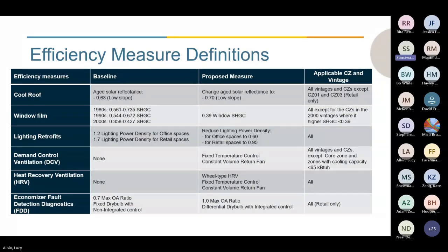And the fifth measure is heat recovery ventilation, or HRV. This measure is a mechanical device intended to remove air from buildings, simultaneously replacing it with outdoor air, and in the process transferring the heat from the warmer to the colder airflow, pretty much just to help with the air transfers. And for the baseline, we don't have an HRV model. And for proposed, we add a wheel type HRV to the space conditioning system to reduce the heating and cooling demands of the building.